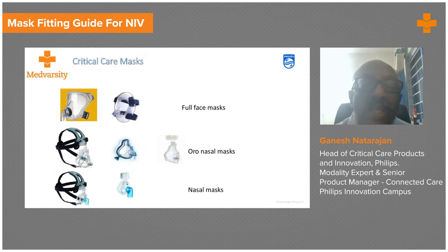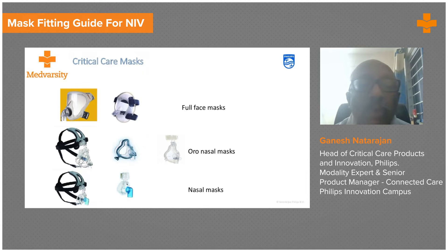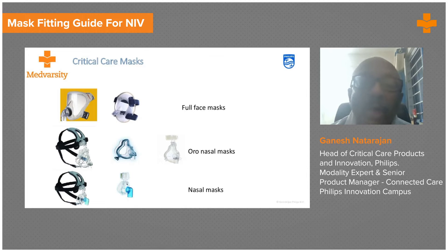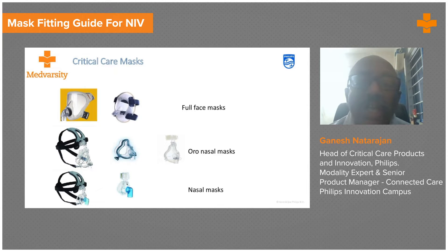A standard elbow used for an invasive ventilator differs from the elbow used for a dedicated non-invasive ventilator, where the exhalation port is built in and the patient can breathe out from there. When purchasing masks, you need to ask for the specific elbow based on whether you are doing non-invasive using an invasive ventilator or on standalone non-invasive equipment.